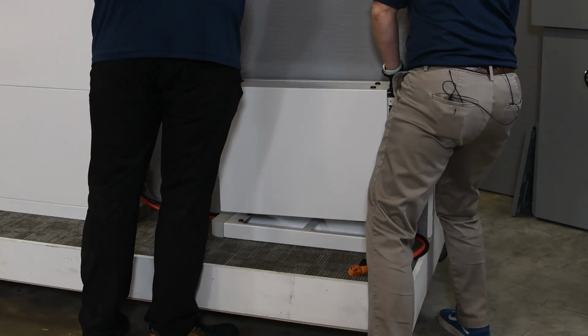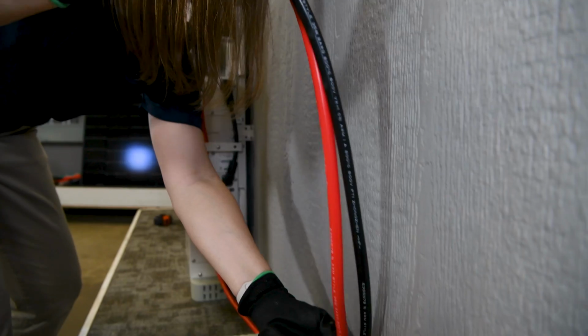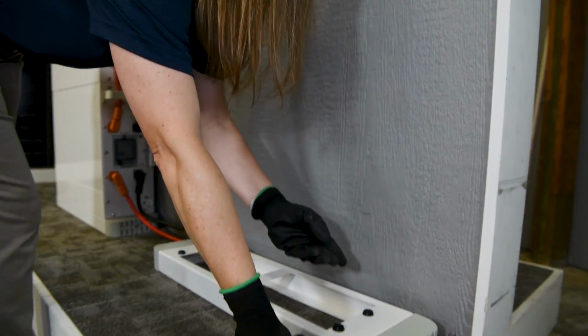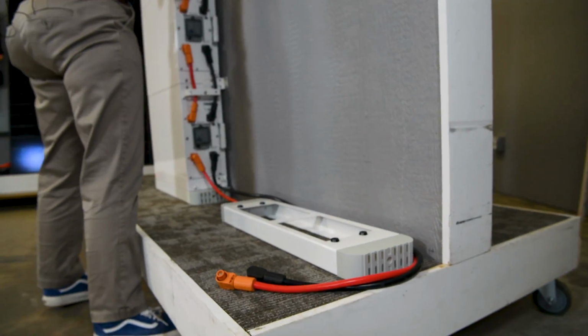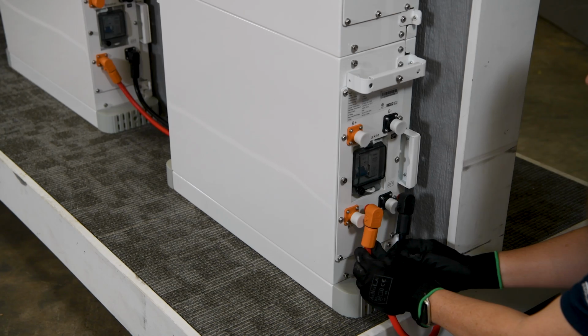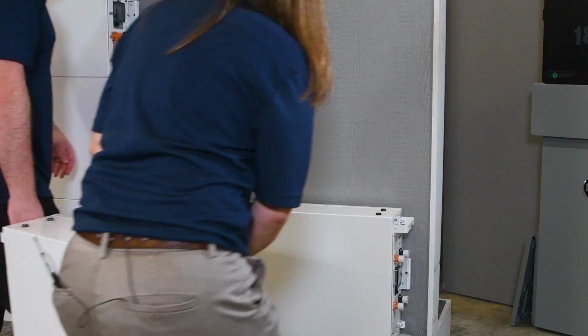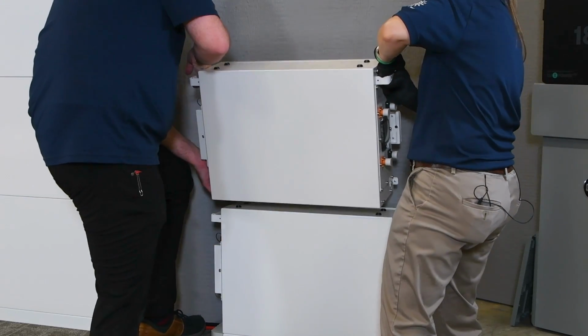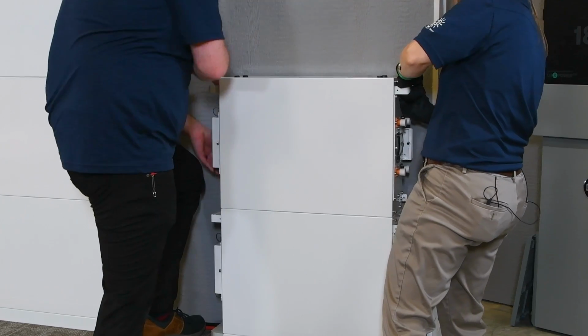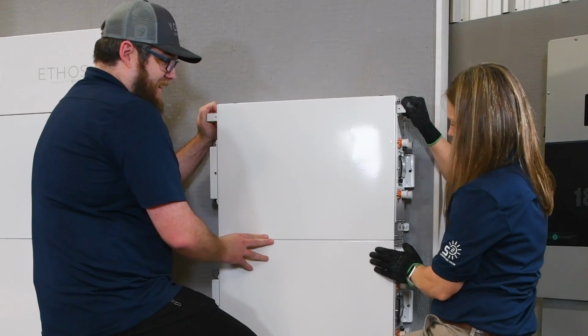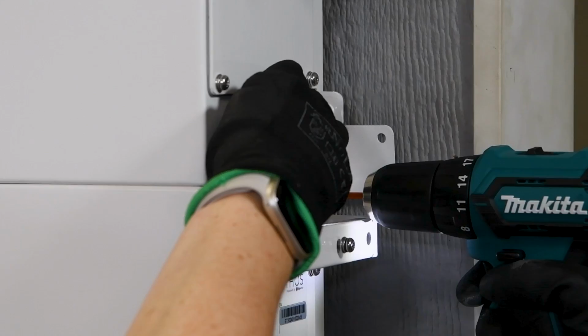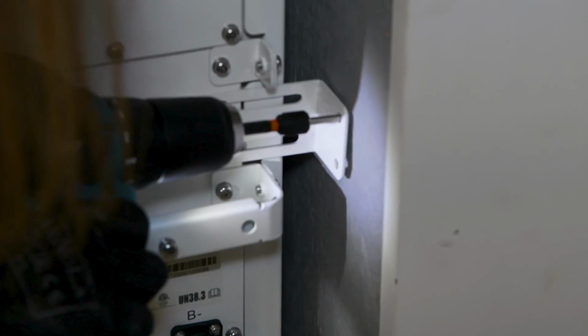Next, I'll stack my first battery module securely on the rack and run my battery cables behind the base to make sure they will reach the terminals before I use the L brackets to secure them to the wall. Once I know the cables will reach, I can continue to stack the other 2 battery modules on top. Once aligned, we'll ensure they're firmly attached to the wall using the L brackets, just as we did with the first stack.